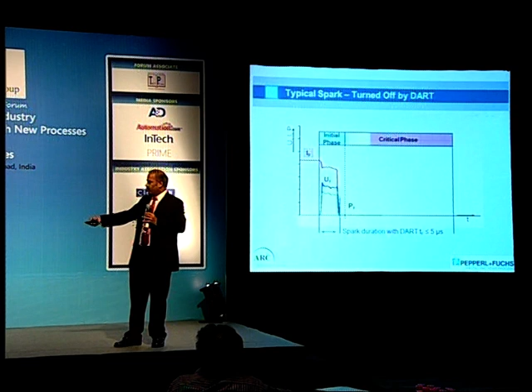So we limit the energy only when there is a problem. If you have a cable break, the circuit isn't going to work anyway, functionally it cannot work. The only thing we have to ensure is safety, and we ensure that by limiting the voltage, current, and power level in less than 5 microseconds.